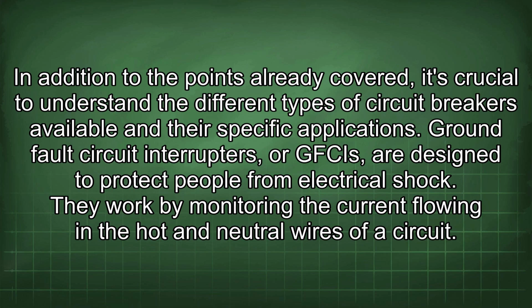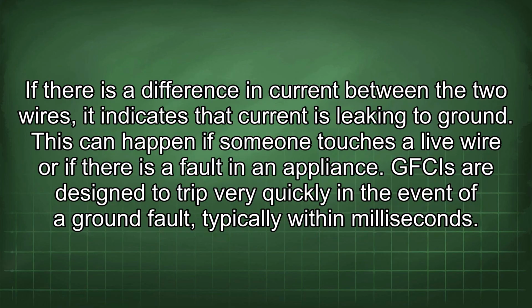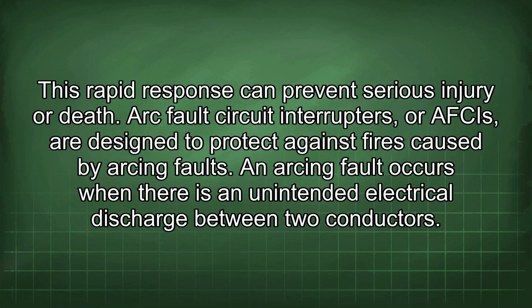In addition to the points already covered, it's crucial to understand the different types of circuit breakers available and their specific applications. Ground fault circuit interrupters, or GFCIs, are designed to protect people from electrical shock. They work by monitoring the current flowing in the hot and neutral wires of a circuit. If there is a difference in current between the two wires, it indicates that current is leaking to ground. This can happen if someone touches a live wire or if there is a fault in an appliance. GFCIs are designed to trip very quickly in the event of a ground fault, typically within milliseconds. This rapid response can prevent serious injury or death.